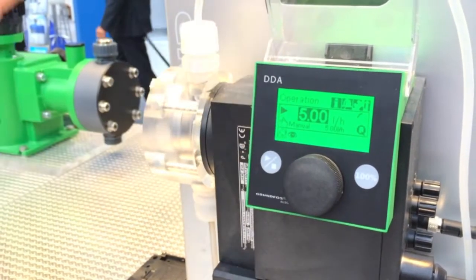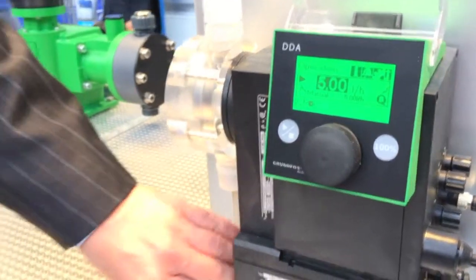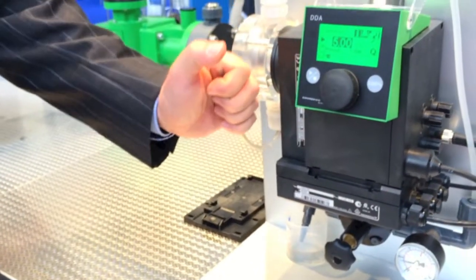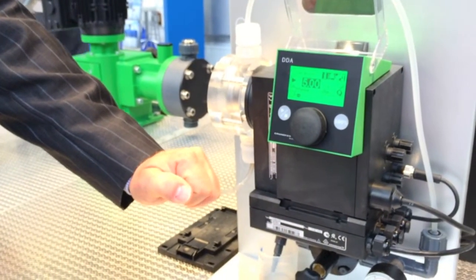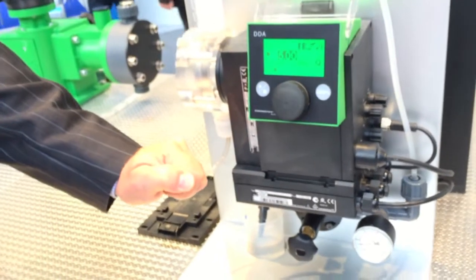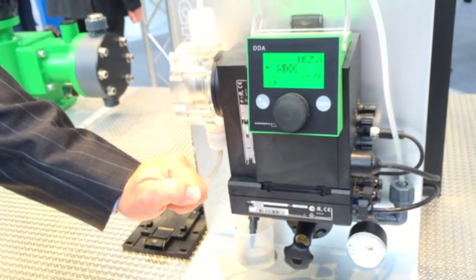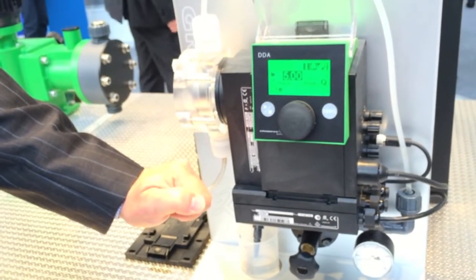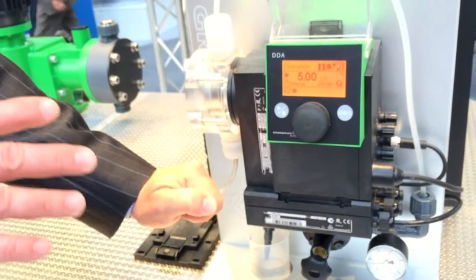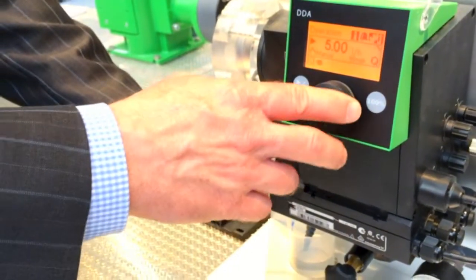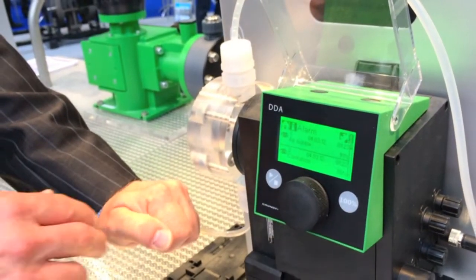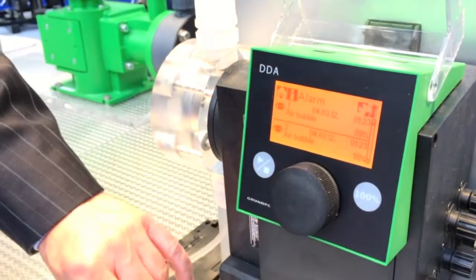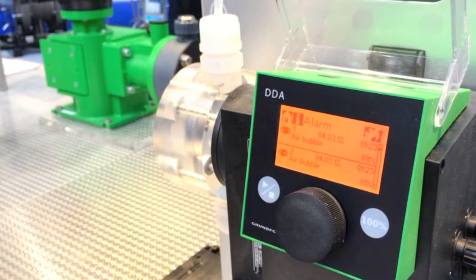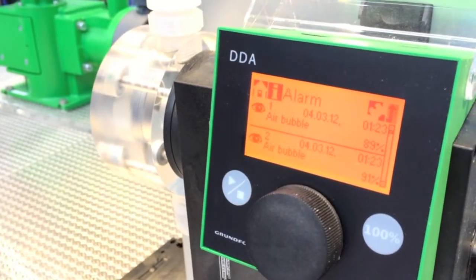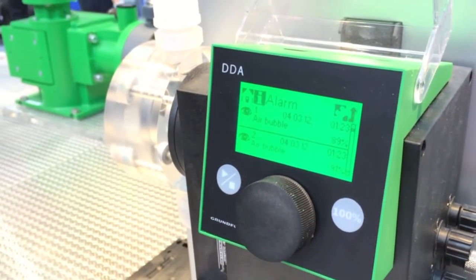Also, if there is something wrong with the pump in the dosing process, we have a colored display. If I create a failure here in the dosing process, for example cavitation, then after a few seconds the display will turn orange, like a warning. It takes a little moment. So now you see that something is wrong in your dosing process. You can go into the alarm menu and directly see what the problem is. For example here, air bubble, and you also see how many percent of air bubbles are in the process, so you have a feeling whether it is a small failure or a bigger failure. And if the pump gets back to normal operation, the display goes back to green.